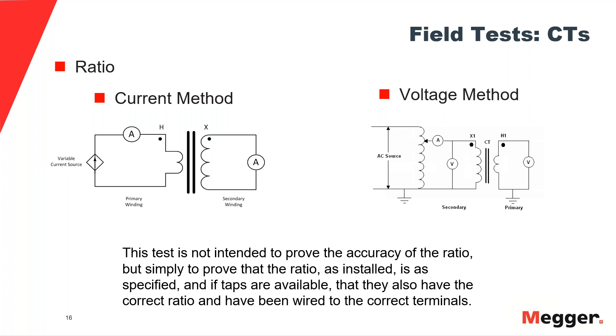A second method is called the voltage method. In this case, I'm using a voltage source, but the connections are different — the voltage is applied not on the primary, but on the secondary. This is done for two reasons. The most important is safety: whatever voltage we are using for the test, we want to ensure that the resulting induced voltage on the other side of the transformer is less than what we're applying. The second reason is practicality — injecting on the primary would require a higher voltage, making the test not feasible to perform in the field.